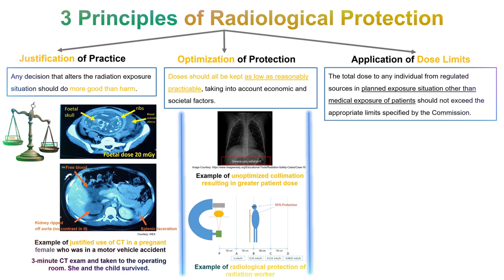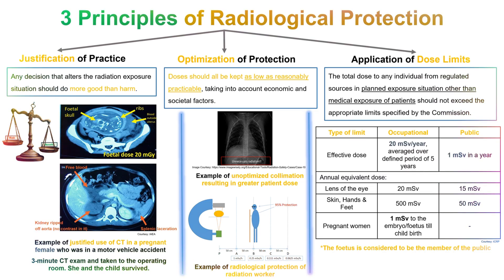The next principle: dose limits. By saying dose limits, we argue that radiation doses to exposed individuals should not exceed the defined permissible amounts of radiation, or should be prevented from exceeding these defined limits. This does not apply to patients' medical exposures. As the definition goes, the total dose to any individual from regulated sources in planned exposure situations, other than medical exposure of patients, should not exceed the appropriate limits specified by the commission. Radiation exposures are both monitored and controlled. The ICRP recommends dose limits based on the radiosensitivity of different organs and a corresponding whole body exposure.